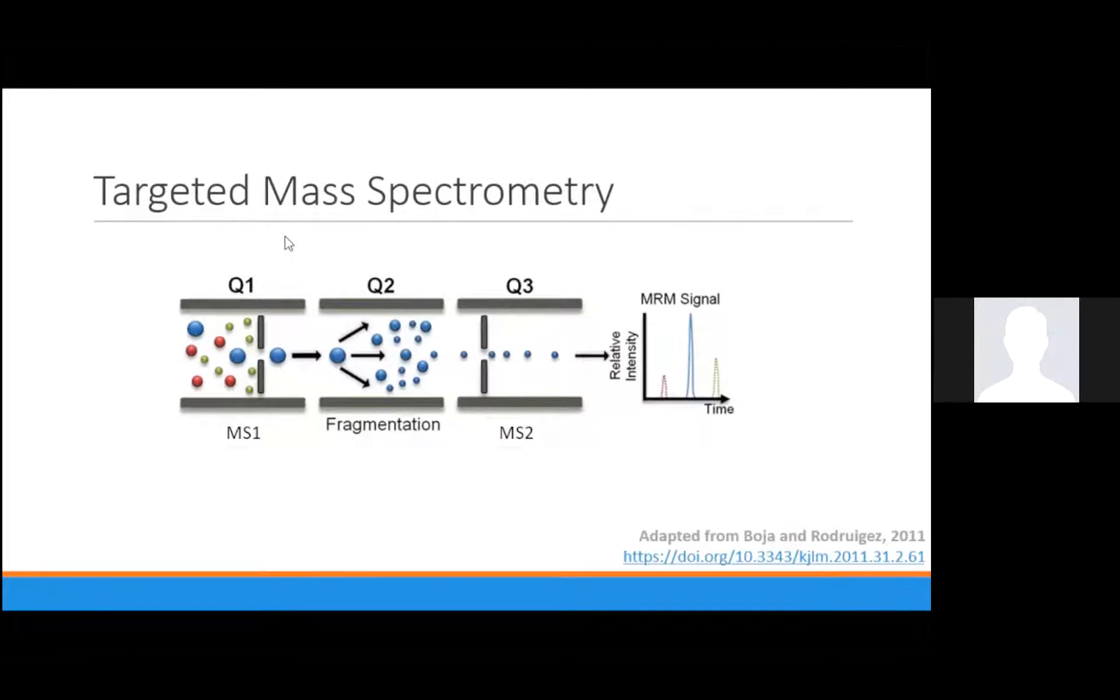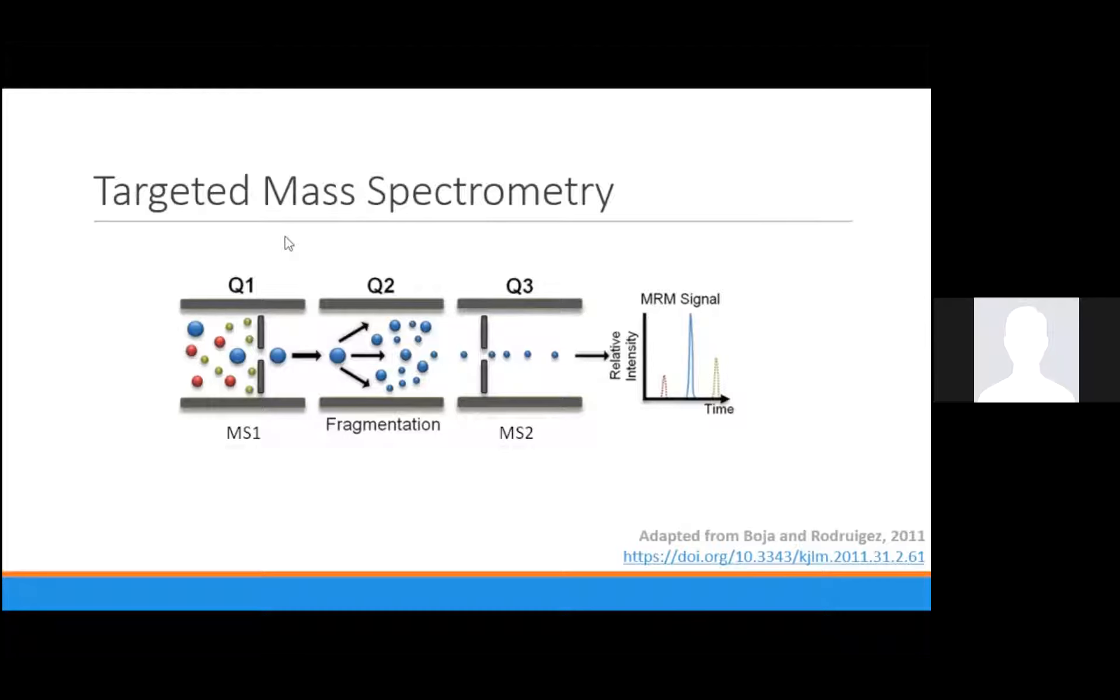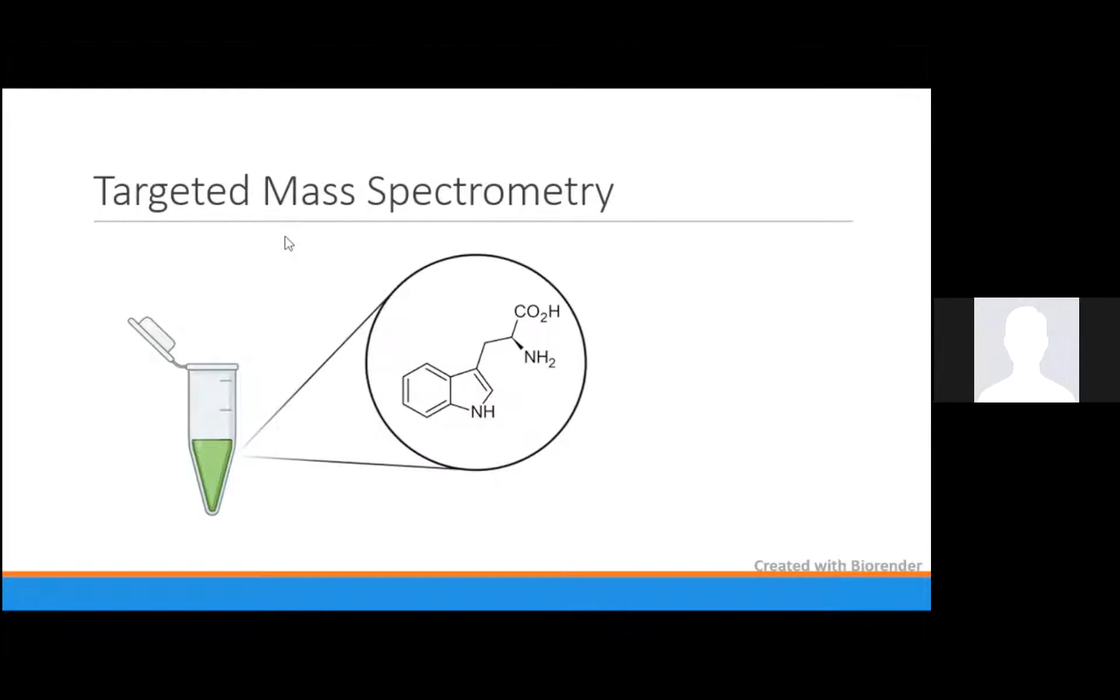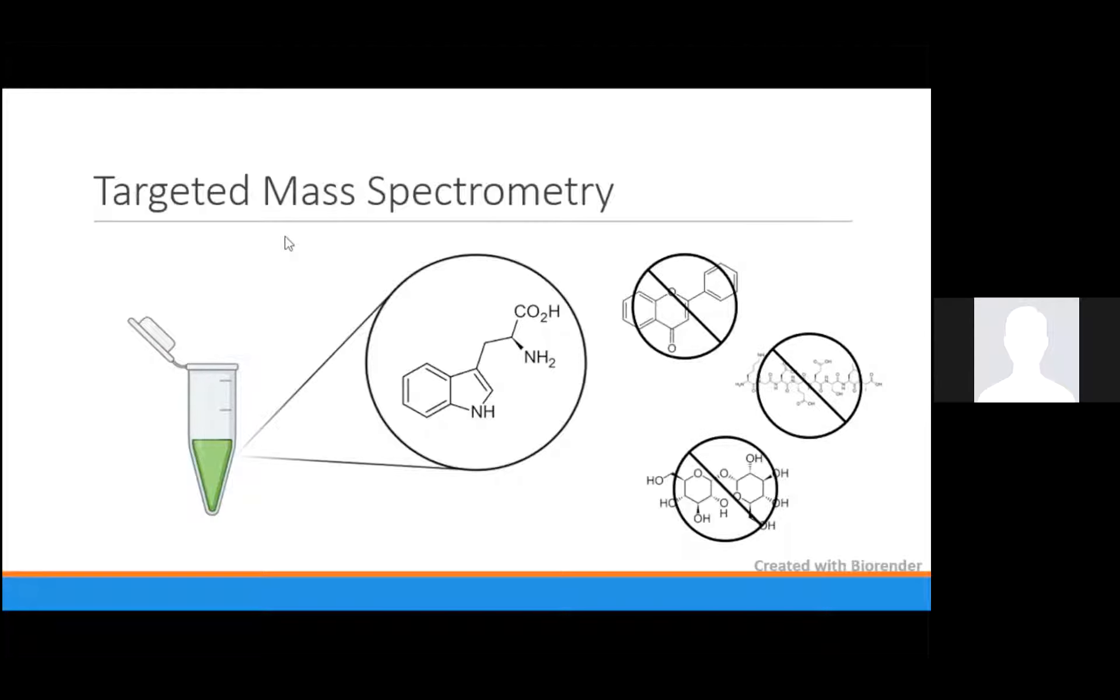To really make sense of this, I think it helps to give a definition of targeted mass spectrometry. This will be covered by my colleague Schwede in another video, but in summary, targeted MS is a technique that uses tandem mass spectrometry, that is, multiple stages of mass filters and analyzers, usually as a form of triple quadrupole. Which specific compounds are able to be detected is predetermined by the researcher, who must run them individually in advance. Without doing this, the instrument and its software will not know which ions to target. This means there is a highly manual process in setting up a targeted mass spectrometer, but that comes with the benefit of simple data analysis, good sensitivity in complex samples, and ease of quantification.